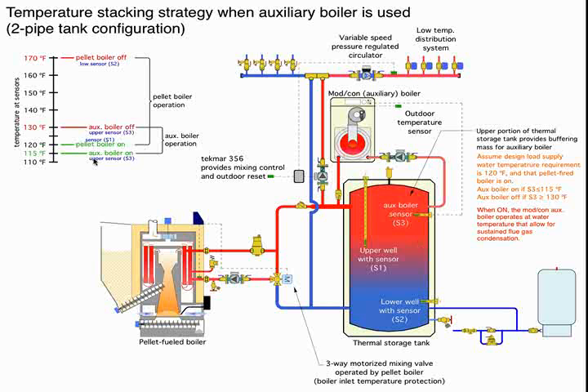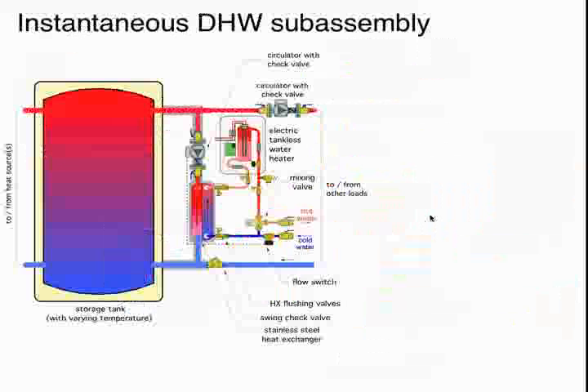Again, here's a system we looked at, or something pretty close to what we looked at earlier, with a pellet boiler, auxiliary boiler, and over here are the temperature scales that show both the pellet boiler on and off condition. Again, it's on at 120 at this sensor. In this case, it's off at 170 at the lower sensor. That's the pellet boiler. The auxiliary boiler is basically on at 115 and off at 130 based on the sensor up at the top of the tank.